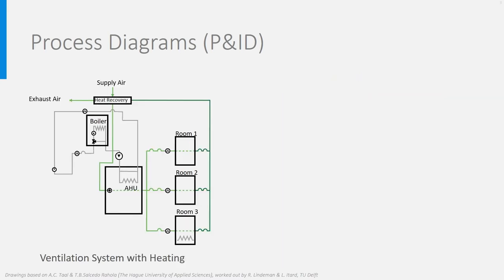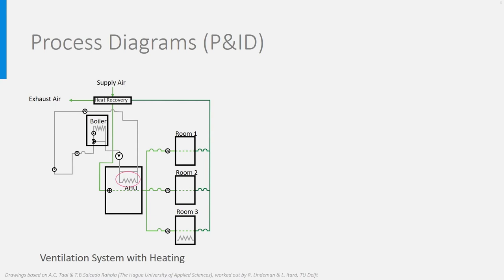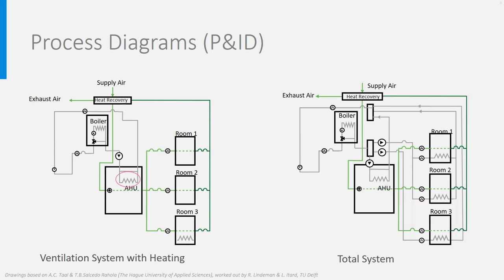In the air handling unit, we need a heater which is a heat exchanger bringing hot water to heat the air when needed. This heat exchanger is connected to the boiler. For now, we don't look at cooling, just heating. In the end, the boiler must provide heat to the AHU and also to the radiators in the room. The P&IDs would therefore look like that. Take your time to study it carefully, looking at the directions of the flows.